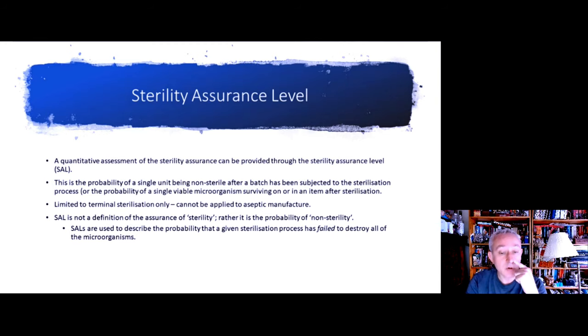Now the sterility assurance level is not a definition of the assurance of sterility per se. Rather, it is the probability of non-sterility. So we're looking at it from the perspective of what is the chance that the sterilization process that we've used has failed to destroy all of the microorganisms. That's probably the easiest way to think of the concept.